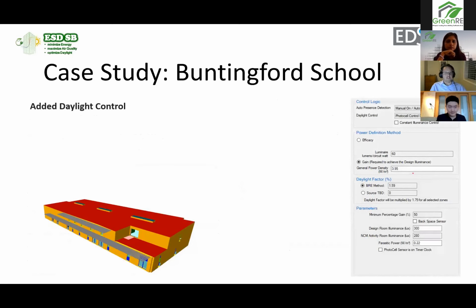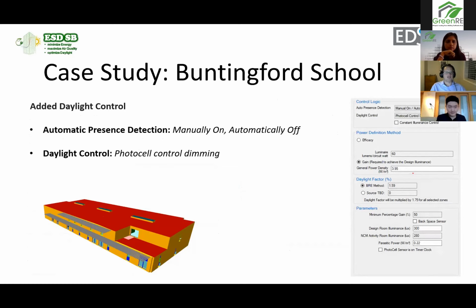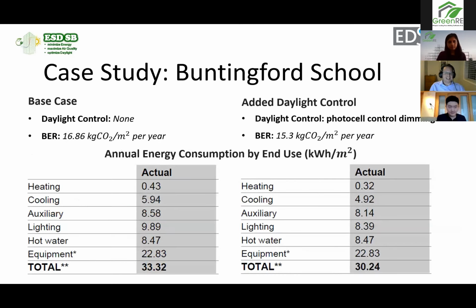One of the most important things we can do to improve our energy efficiency is daylight control. So once again, we're going to have automatic presence detection. But this time we're going to have daylight control, photocell control dimming. So as it's brighter in the room, the lights will turn off. Same general power density, to make it more of a like-for-like check. And now we're getting even more reduction. That reduction is in both the lighting and the cooling, as you'd expect, as the lighting heats up the space and we require cooling to prevent that. So we've gone from a value of 16.86 down to 15.3.